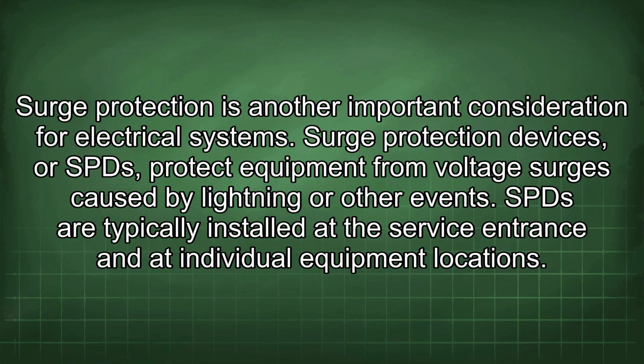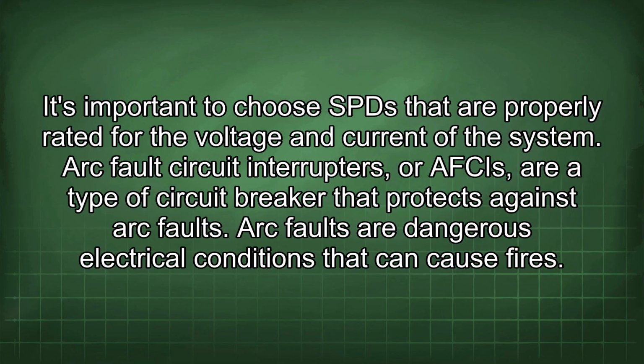Surge protection is another important consideration for electrical systems. Surge protection devices, or SPDs, protect equipment from voltage surges caused by lightning or other events. SPDs are typically installed at the service entrance and at individual equipment locations. It's important to choose SPDs that are properly rated for the voltage and current of the system.